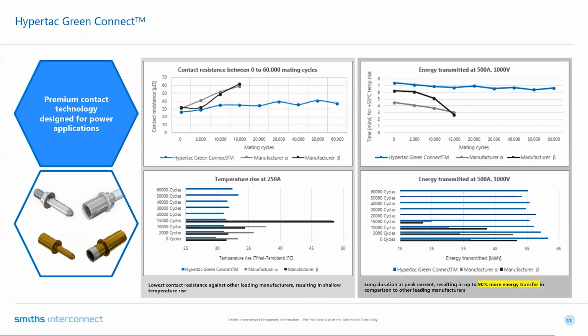We ran this test comparing ourselves against two other leading manufacturers in power connectors using their contact technology. What's evident from the graph on the top left is how, as the material degraded with the number of mating cycles, the contact resistance remained stable with the Green Connect, whereas the two other leading manufacturers started well but degraded.